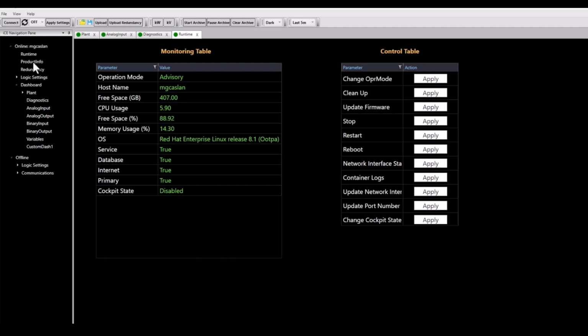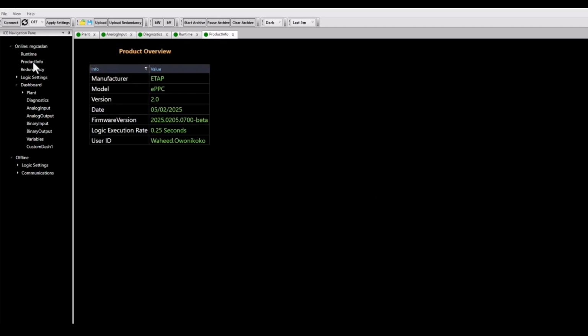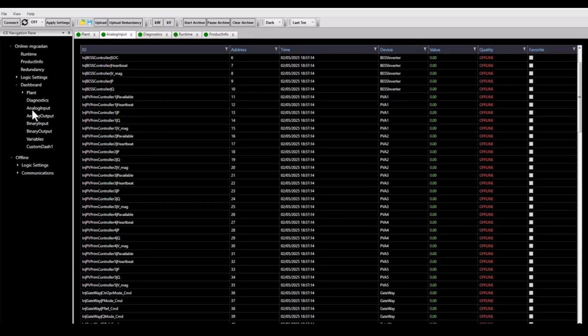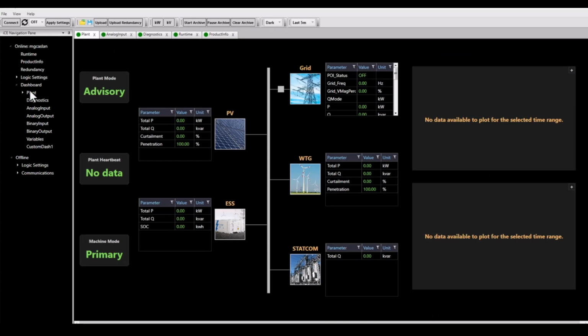Once the deployment is complete, the EPPC begins operating in real time. It establishes communication with the DNP3 server and continuously reads live measurements either from the SCADA or the ETAP real-time simulator. Based on the control logic we defined, EPPC performs the necessary internal calculations and sends control commands back to the SCADA or directly to the power plant.